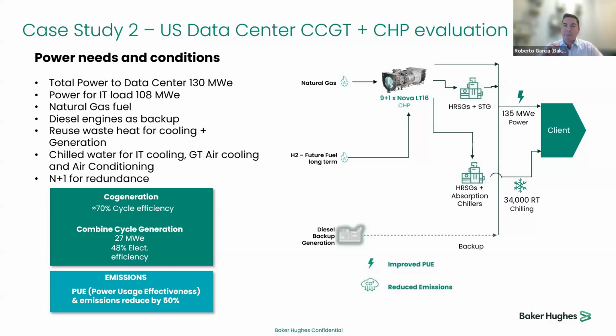With this configuration, the level of efficiency is much higher, close to 70% for the whole cycle. The combined cycle portion efficiency is around 48%. One of the main objectives for this specific customer is to improve the PUE, the power usage effectiveness, for this data center—they are looking to reduce it as much as they can. This configuration, knowing they don't have the grid available, offers a big improvement, close to a 50% reduction in their PUE.